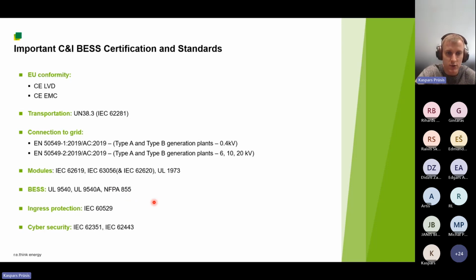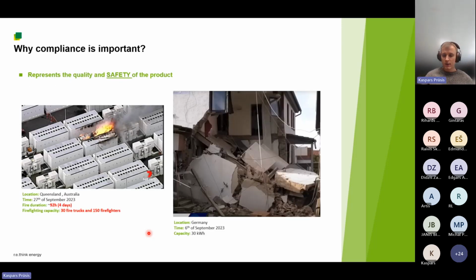Then there's ingress protection, IP class, and also becoming more important is cybersecurity requirements. They are mostly for utility scale projects, but they are probably going to be used for C&I as well. And if we talk about standards, why are they important? On this slide, I wanted to show two examples of what happens when you don't follow standards or there's an issue with the batteries itself.